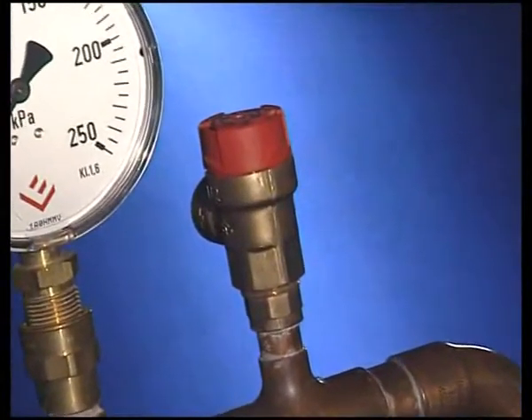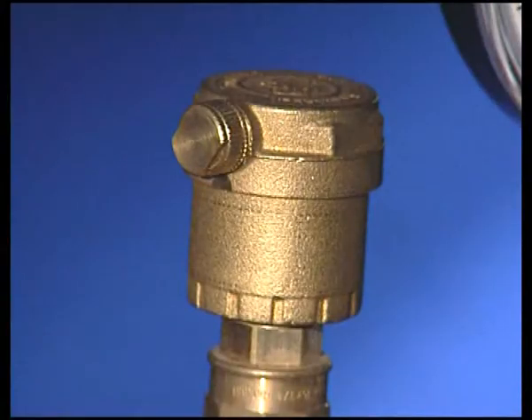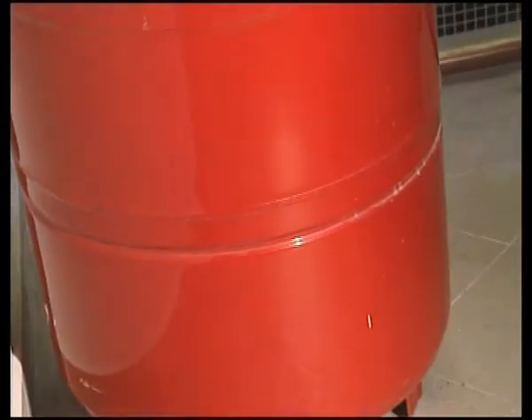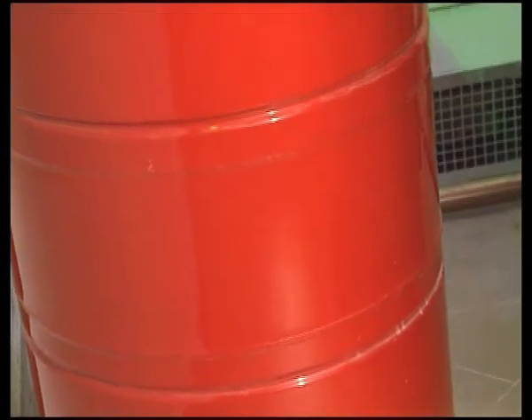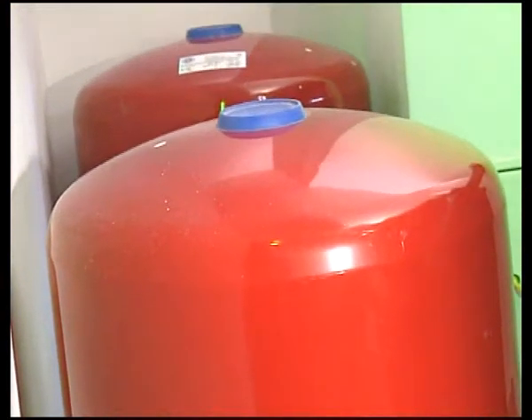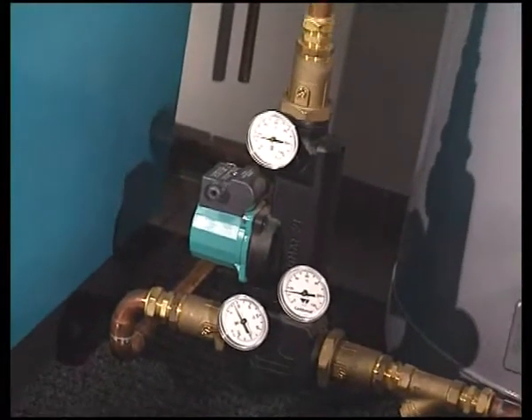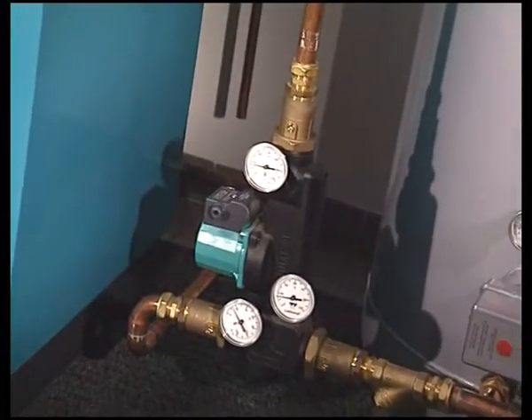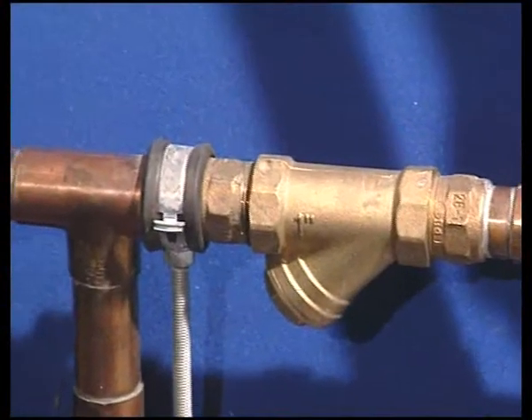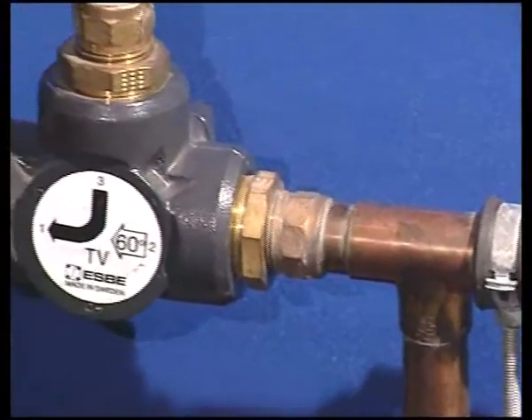The system includes other components like the safety valves, bleeding valve, pressure gauge, and so on. Very important is also the expansion vessel, which can be open or closed type. In front of every important component, like the Ludomart 21 thermoregulator, we must not forget to install a filter for their protection against contamination. This applies to new systems as well.